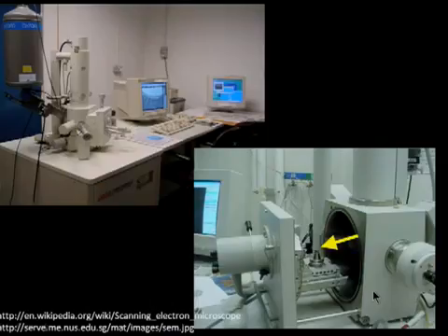There are variations on this that let you, for example, use a little bit of moisture or seal your sample in very, very small, you could say, little boxes. But by and large, what you put in an electron microscope has to be vacuum compatible, so it can't be wet and so on. And also the sample has to be electrically conductive because that electron beam that scans across the sample is going to charge your sample, and you need to have a means of dissipating that charge to maintain a stable imaging condition.